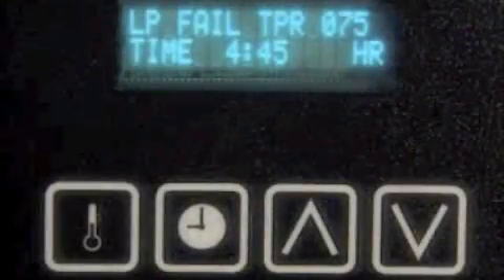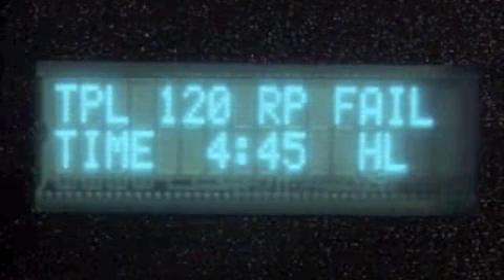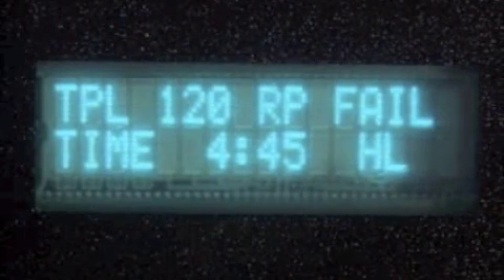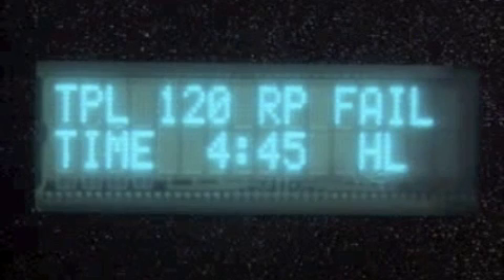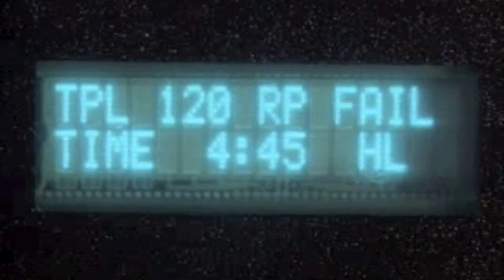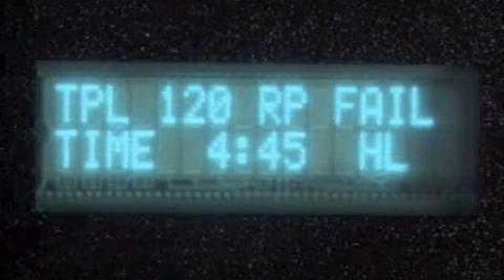Your new Impinger is equipped with 3 diagnostic messages to help you troubleshoot a specific problem yourself, or at least help you narrow it down. The messages you might encounter on the digital display are 1. LP, left probe fail, or RP, right probe fail. This occurs when there's no temperature being sent to the controller from the baking chamber. This generally means a malfunctioning or failed thermoprobe.